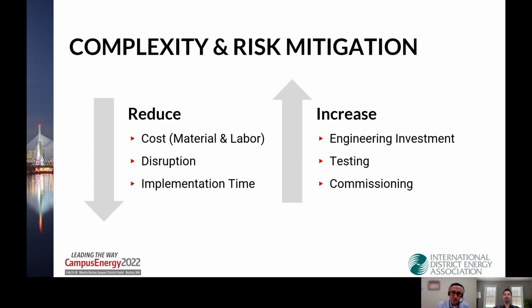Converting all these steam distribution systems over to hot water made the system simpler, which was one of the boxes we needed checked. Instead of operating and maintaining steam converters, condensate systems, traps, receivers, and pumps, in a lot of cases all that went away and we were left with just an injection valve, which is much simpler.